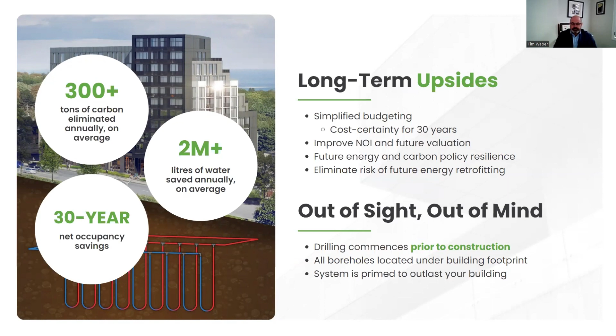The other thing too is because it's underneath the building and made out of high density polyethylene pipe, the same pipe that gas companies use to transport natural gas, it will outlast the building. It's designed for an 80 to 150 year life cycle. It doesn't get impacted by UV rays. It's under the building, it can't be fractured, it can't be damaged, it's protected—can't be drilled into or hit by an excavator. It will literally outlast the building.